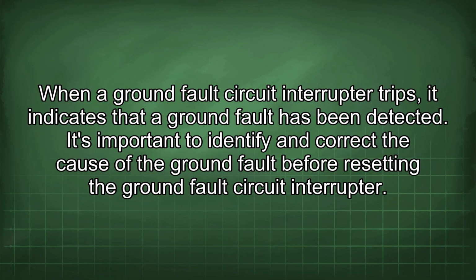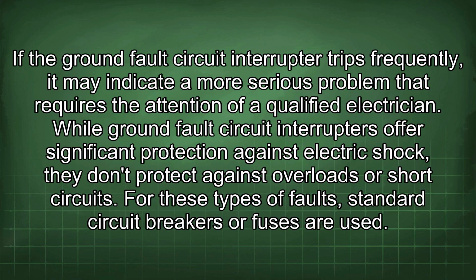When a ground fault circuit interrupter trips, it indicates that a ground fault has been detected. It's important to identify and correct the cause of the ground fault before resetting the ground fault circuit interrupter. If the ground fault circuit interrupter trips frequently, it may indicate a more serious problem that requires the attention of a qualified electrician. While ground fault circuit interrupters offer significant protection against electric shock, they don't protect against overloads or short circuits. For these types of faults, standard circuit breakers or fuses are used.